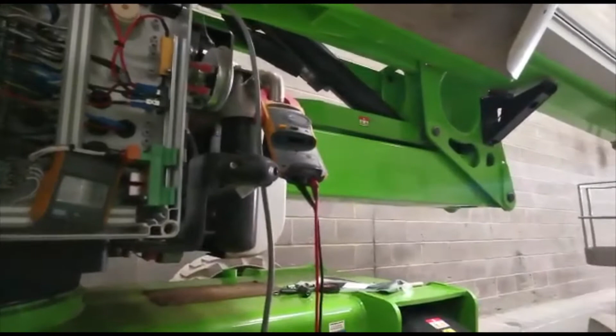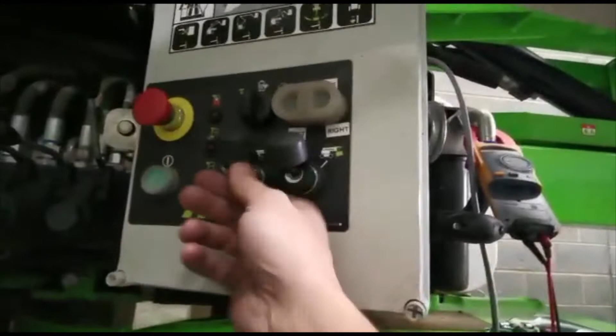Sensor outputs in base. So in the base we have 4 outputs, 2 x-axis, 2 y-axis. In the cage is only 1 output, and then what we had to do, if the outputs are good, is run a calibration. So let's see if I press the button. Yeah, the motor is running. Let's try to restart the machine just to see if the problem is gone for good. Okay, so it's all working fine.